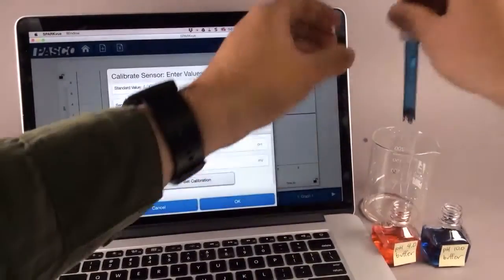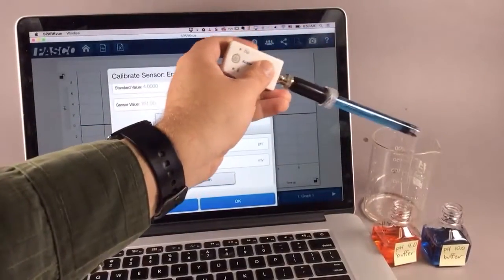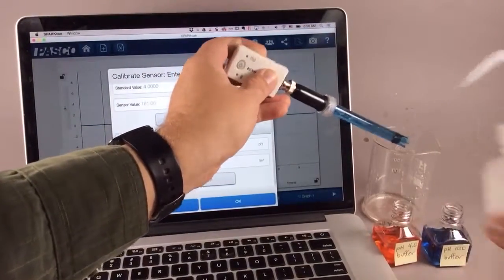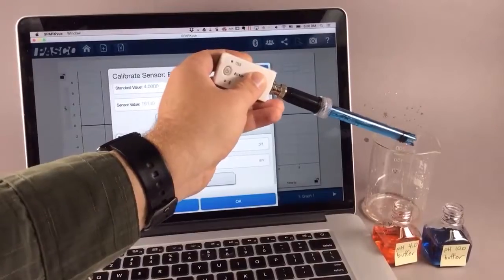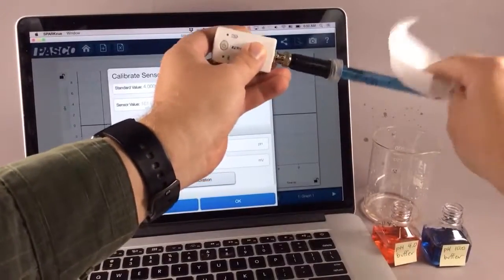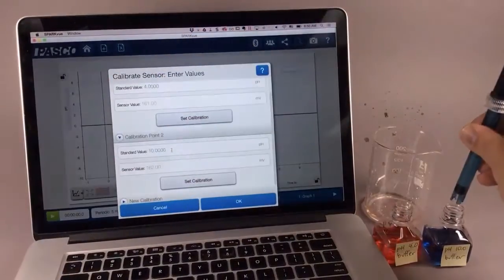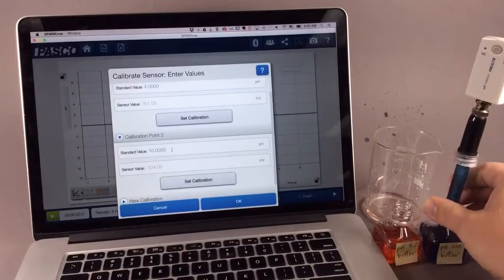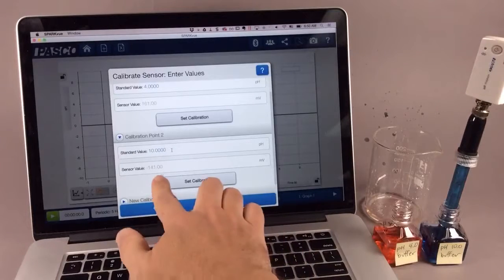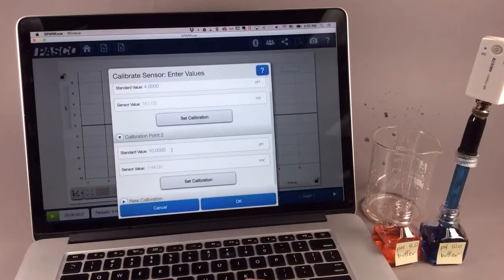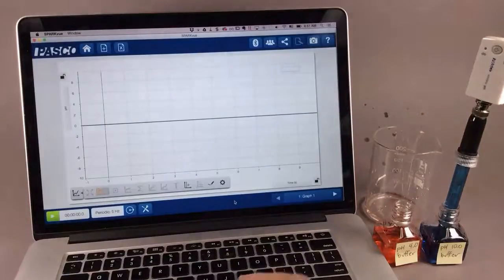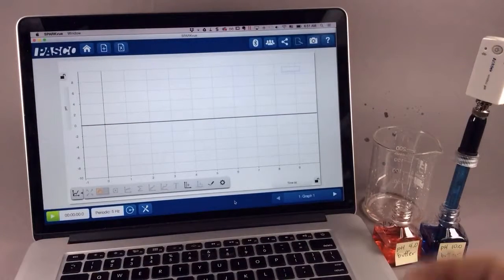So I'll rinse the pH electrode once again. Blot it dry. Place it in the second calibration solution. And I'll wait for this reading to stabilize. Once it's stable, I'll choose Set Calibration for the second point and press OK. My pH sensor is now calibrated, and the calibration will actually remain with the sensor itself.